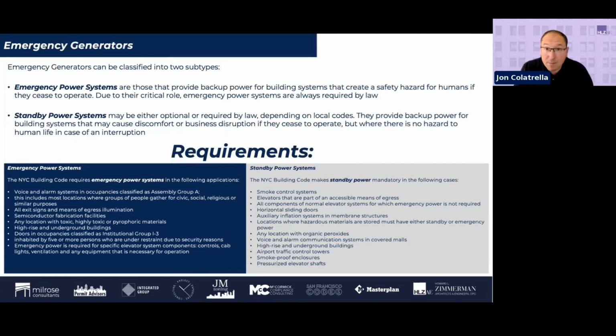These requirements include, at minimum, emergency lights, the fire alarm, and an elevator serving all floors of the building. So if you have a high-rise major building and fall under the category of requiring a generator, those systems—and possibly others—at minimum will have to be connected.